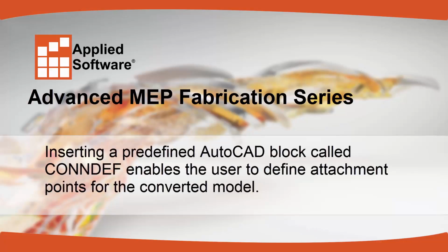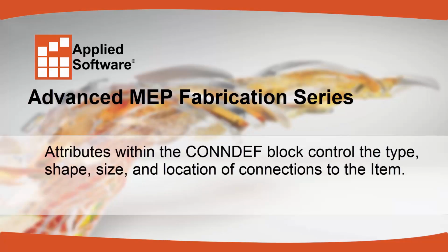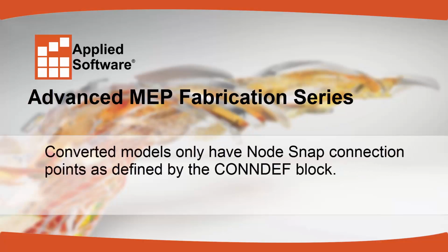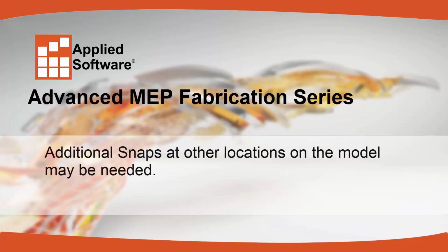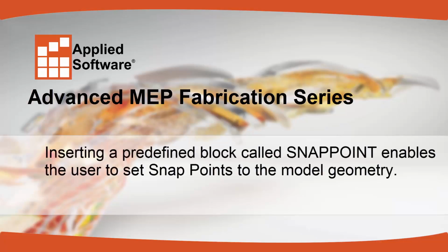Inserting a predefined AutoCAD block called CONNDEF enables the user to define attachment points for the converted model. Attributes within the CONNDEF block control the type, shape, size, and location of connections to the item. Converted models only have node snap connection points as defined by the CONNDEF block. Additional snaps at other locations on the model may be needed.